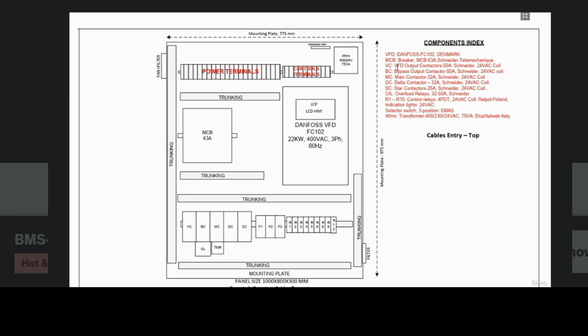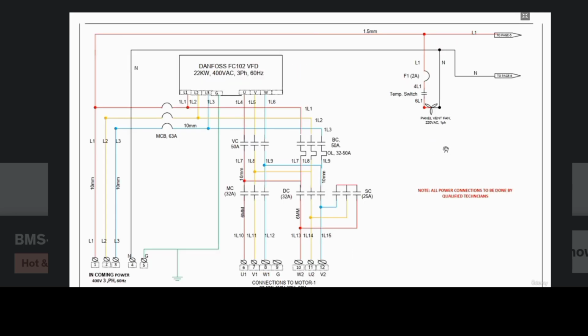So from here you can see that VFD VC is the VFD output contactor. We will go into details about that. This is the power circuit of the VFD. Here we have the incoming power to the MCC panel. Then this is our Danfoss VFD. This is the bypass circuit. This is the star delta contactor. These three contactors are for star delta. And these two contactors are used to select either the VFD or the bypass mode.